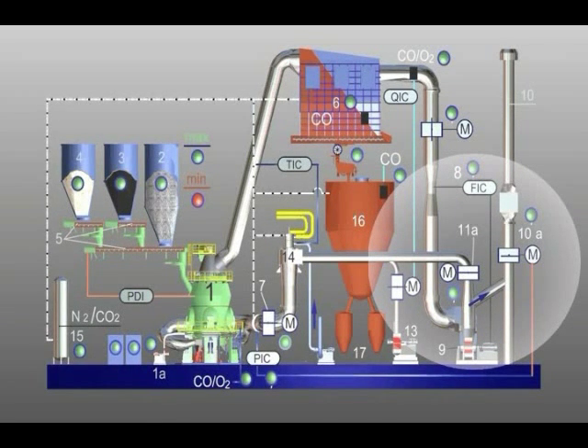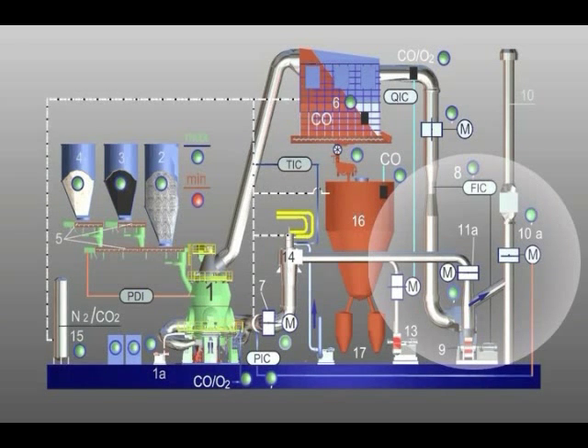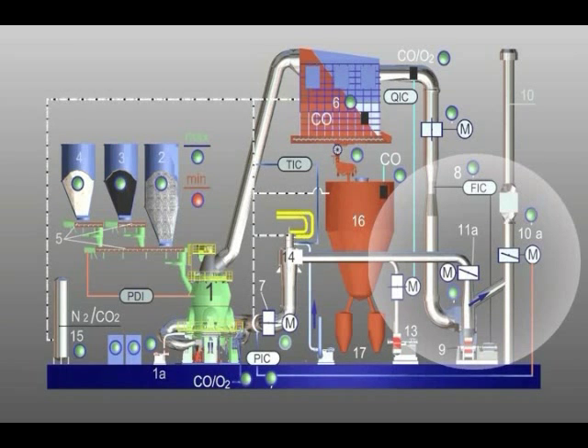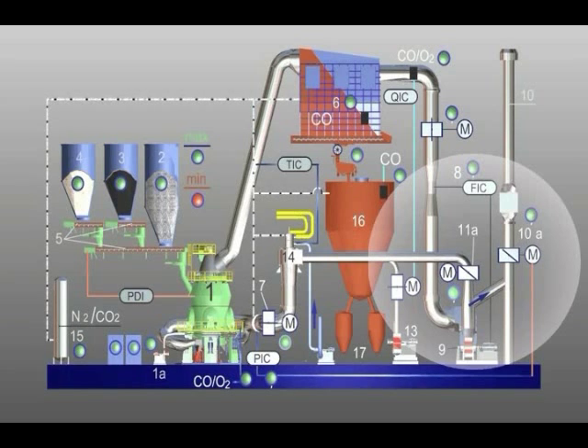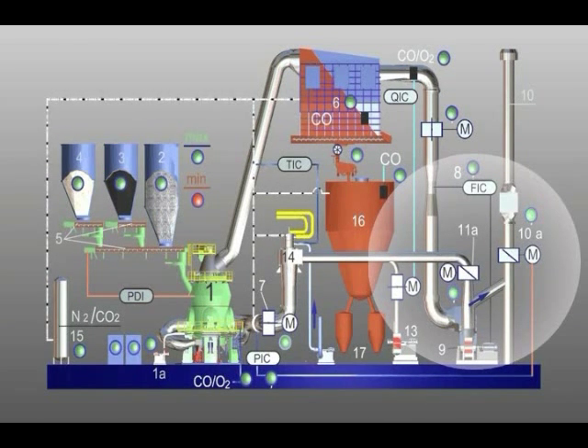The flap in the return gas duct, position 11A, and the stack flap, position 10A for controlling the volume flow of exhaust gas, are moved to their start position. The volume flow of process gas is measured via a venturi tube, position 8. This volume flow is regulated by means of the vane control, position 9.